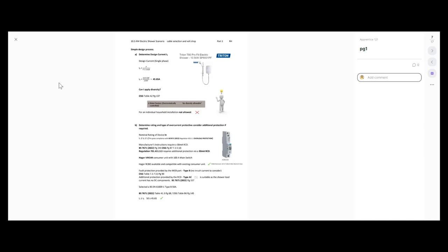Would I install a Type AC? Probably not for the cost — I'd probably put a Type A. Most wholesalers have kind of moved away from stocking ACs on the shelf anyway now, so you're getting Type A's by default whether you like it or not. We're more likely to see them pulling B's onto the shelf rather than ACs. It would most likely be receiving a Type A, but it is important to note that this is one of the examples where you could use a Type AC, and they are becoming more limited as time moves along.